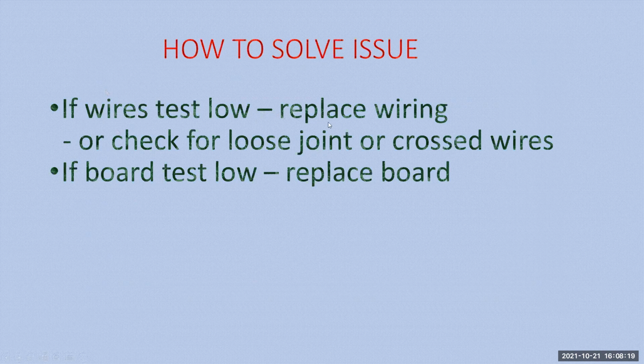Here we are. Wires test low, replace wiring or check for loose joint, crossed wires. If board tests low, replace the board. Always make sure to double check your wires. That's probably 75% of the time: your problem is going to be a wiring issue, not a mechanical equipment issue.